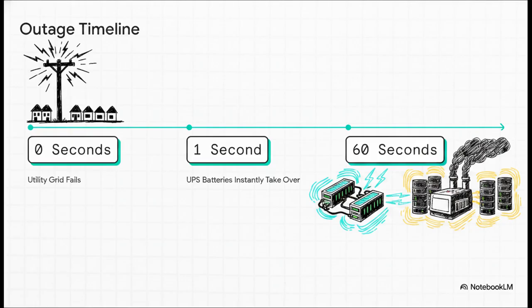At exactly 1 second, those massive UPS batteries have already instantly taken over, keeping the servers perfectly humming. This gives the facility the crucial runway it needs. Over the next minute, those massive diesel engines outside start firing up, and by 60 seconds, the diesel generators reach full output, seamlessly taking the heavy electrical load over from the UPS batteries. It is a perfectly choreographed handoff.